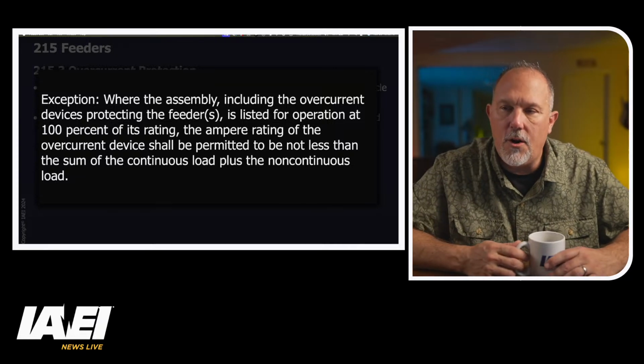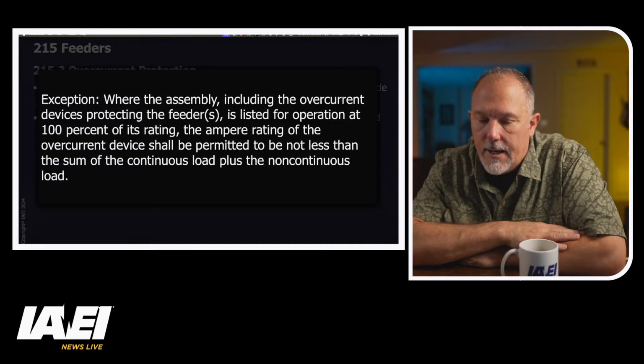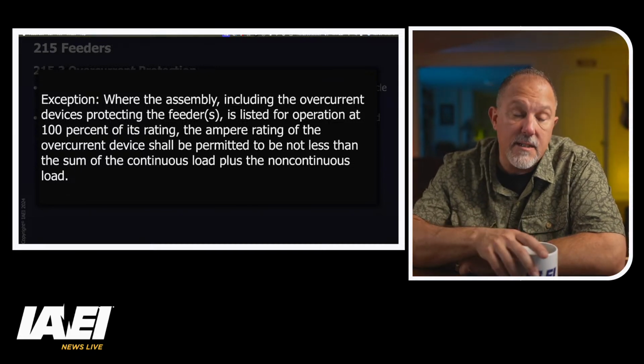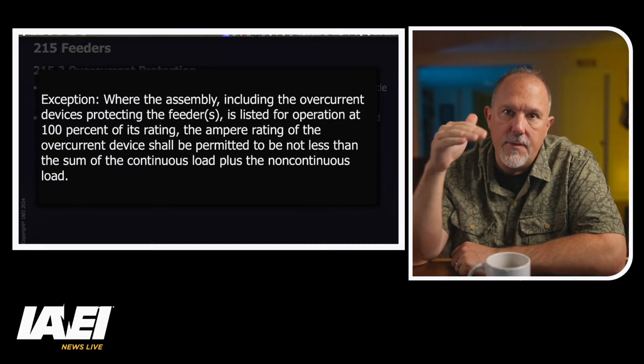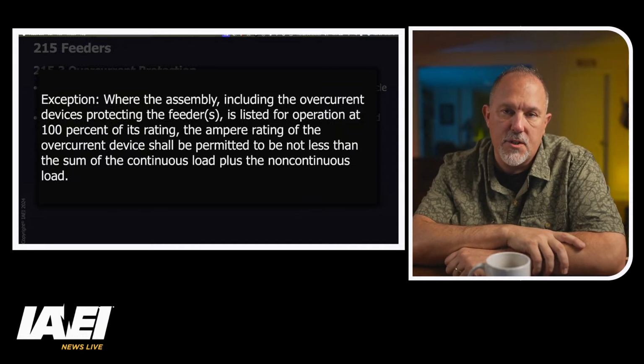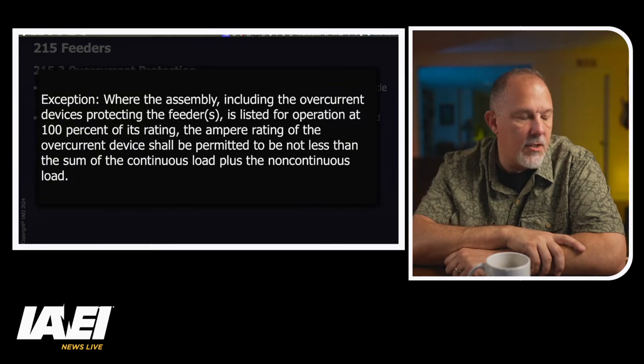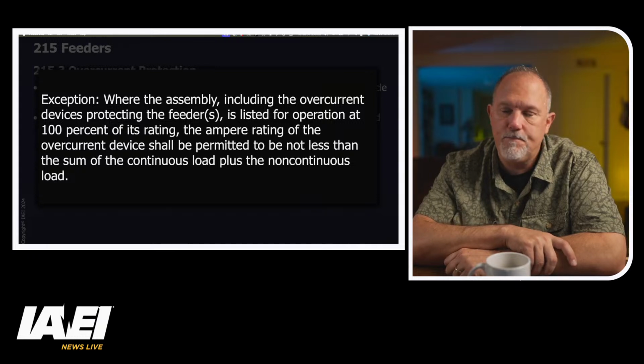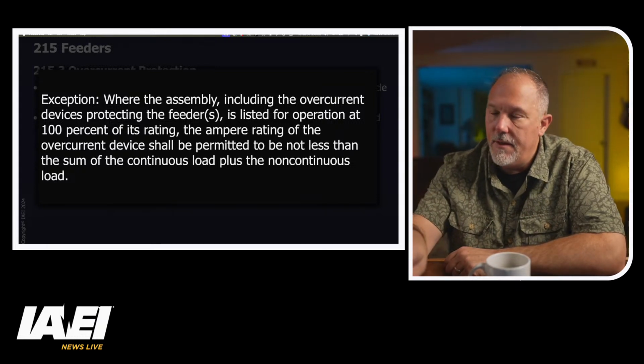Now, I just had a phone call on 100% rated equipment yesterday, actually. A gentleman calls me up and he says he has an installation where they've done the load calculations and they've exceeded this 80% rule for the overcurrent protective device. And so now he's looking at just buying a 100% rated circuit breaker. Here's the problem with that. When you're dealing with 100% rated applications, it's not just about buying a 100% rated circuit breaker. You've got to think about the equipment within which it is installed. If you use a 100% rated circuit breaker, the panel board or switchboard has to be also 100% rated.